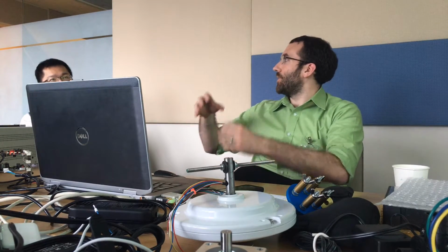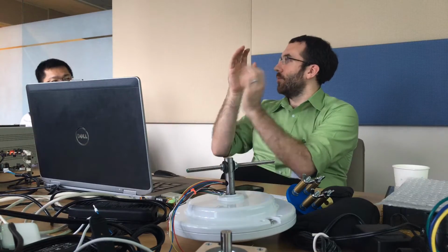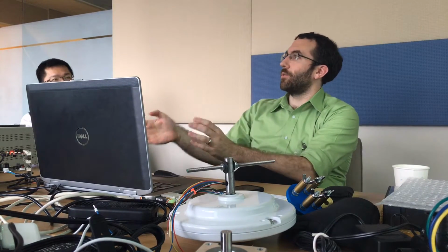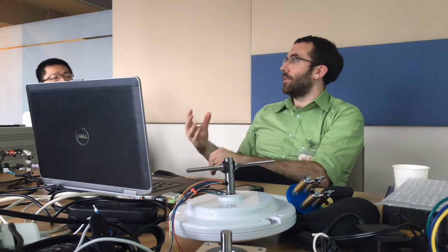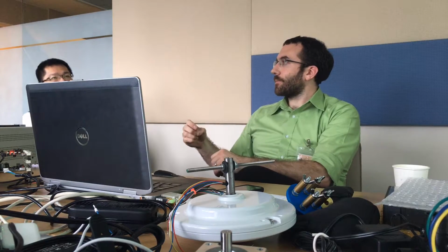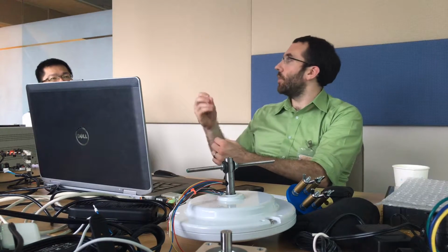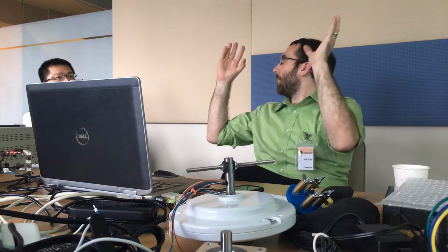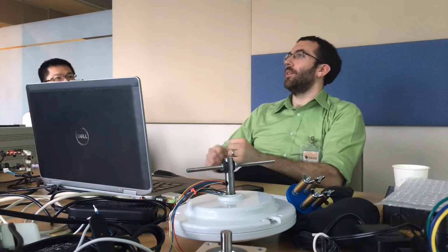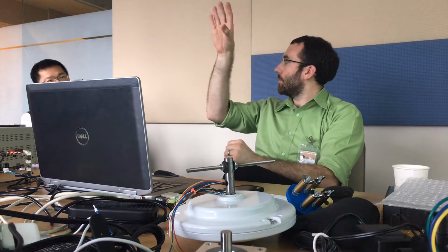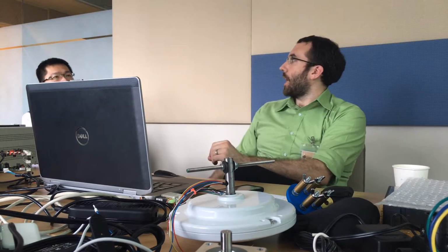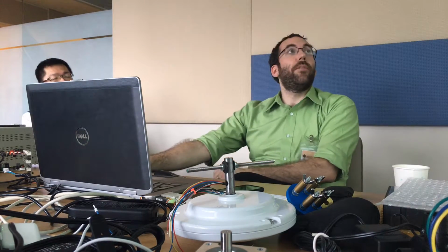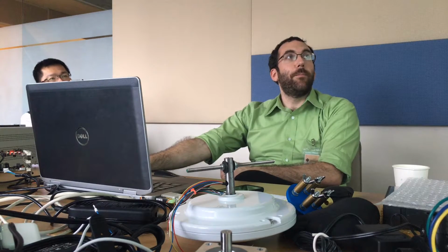This is what controls the drive. This is what says run as a speed controller, run as a current controller, run as a voltage controller. It also monitors the drive for faults. When we were seeing those peak over current faults, the DSM was triggering that and saying there's a problem, we need to stop. So it issued the problem up to the customer, but also stopped the drive. All the fault handling is built into this DSM.